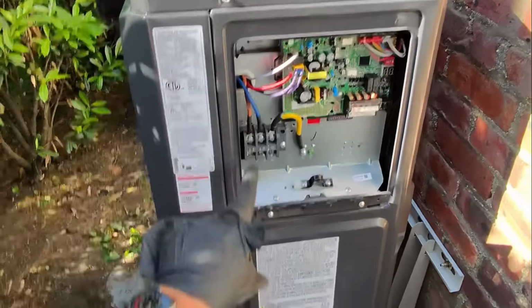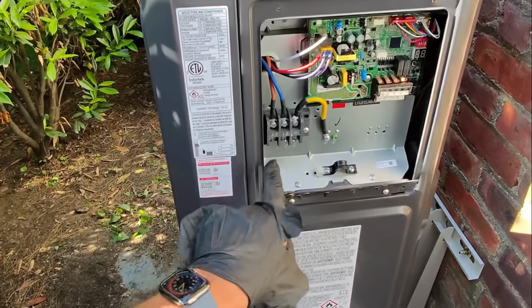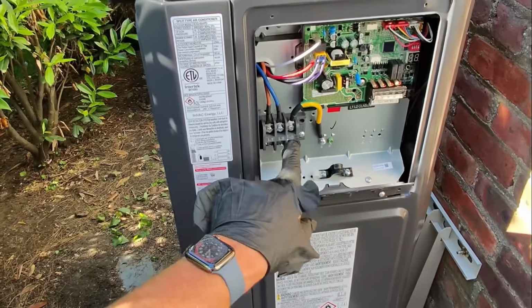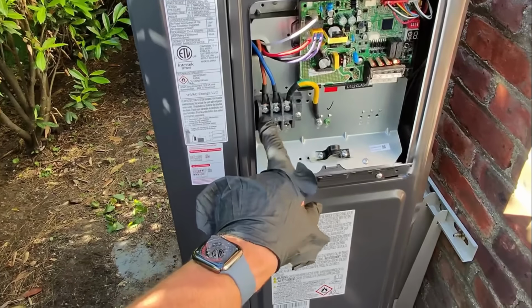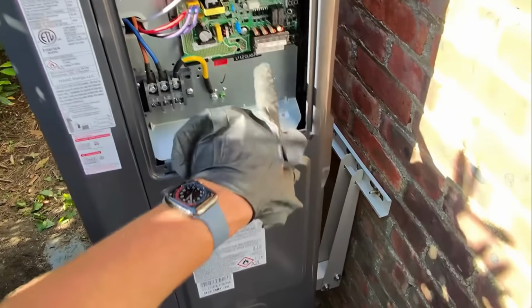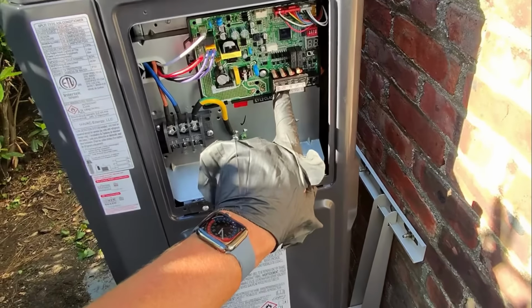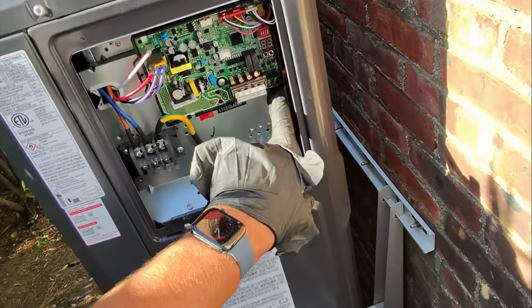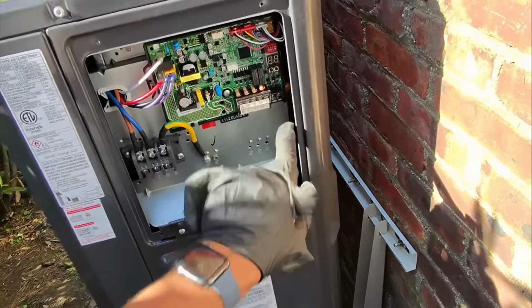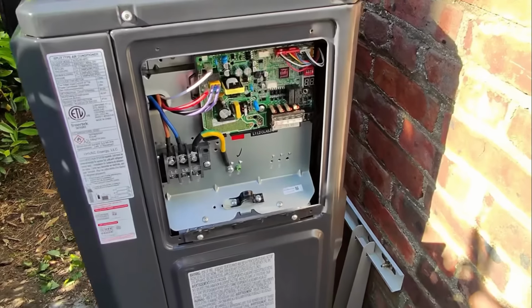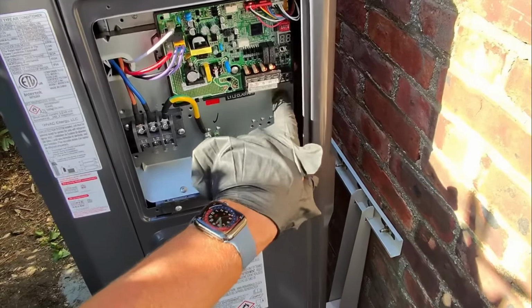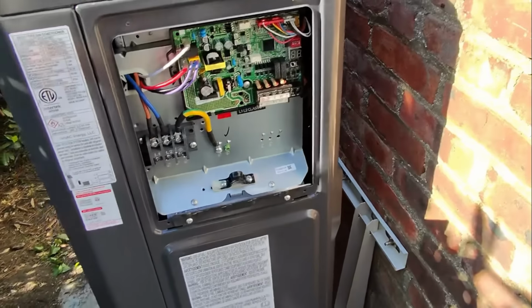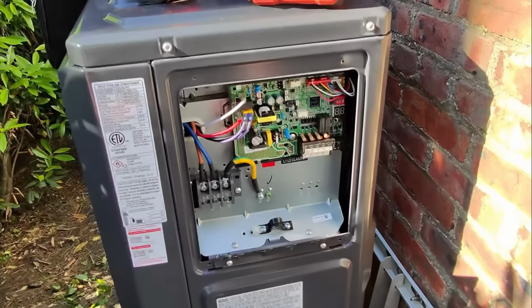There it is. Here's our line voltage incoming. L1, L2, ground. It only takes 208, 240 volts, remember that. Here's the 24 volt connections, and all the way on the bottom right is S1, S2, those are your two serial port connections. Never, ever, ever put 24 volts on those serial port connections or you'll fry that board.